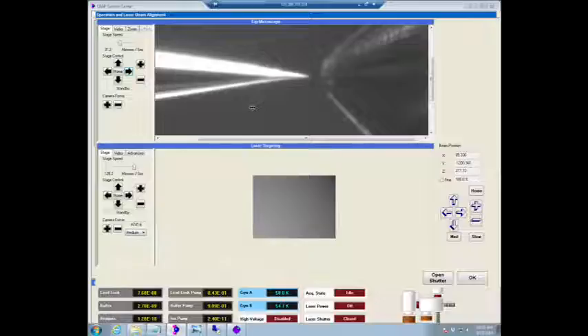So the location of the sample in front of the local electrode is not really just given by... You might be compelled to think that you put the sample just where it would cross over from here to here, or sort of at the end of the cone. But the thing with that is that the hole is not always in the middle, and the local electrode is not always straight at the end. So there's quite a lot of variation in manufacturing. So sometimes the good measurement point will be here, sometimes here, sometimes here, and so on and so forth.